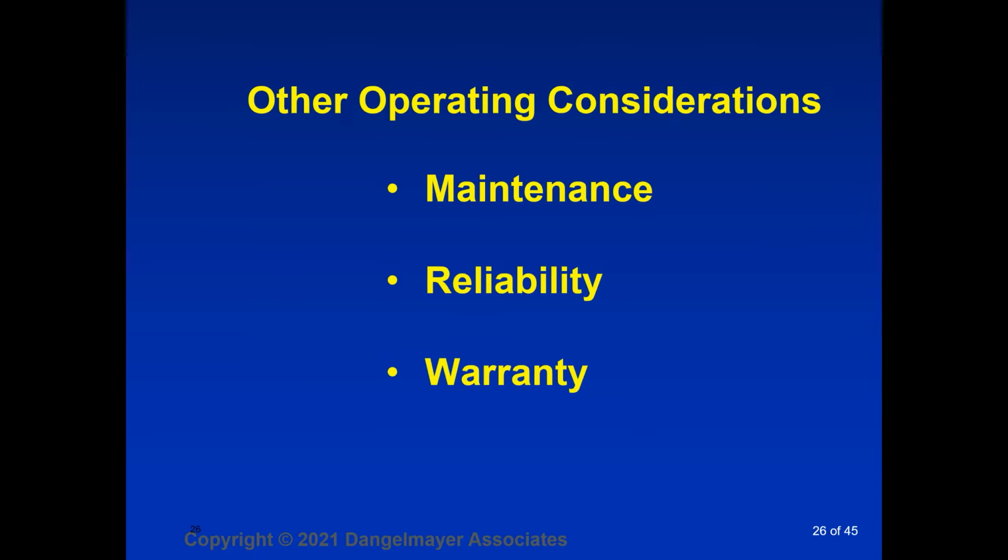The best I can say is that the maintenance interval on an alpha ionizer is the longest, and that's typically 12 months. But within that 12-month period, every other type of ionizer will need multiple maintenance operations.